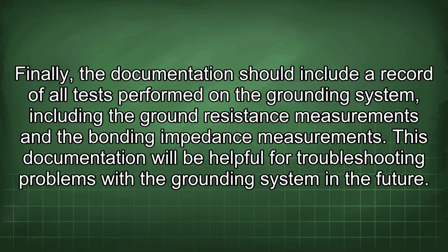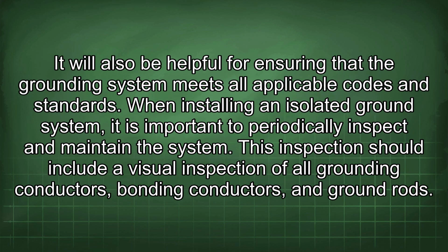Finally, the documentation should include a record of all tests performed on the grounding system, including the ground resistance measurements and the bonding impedance measurements. This documentation will be helpful for troubleshooting problems with the grounding system in the future. It will also be helpful for ensuring that the grounding system meets all applicable codes and standards.